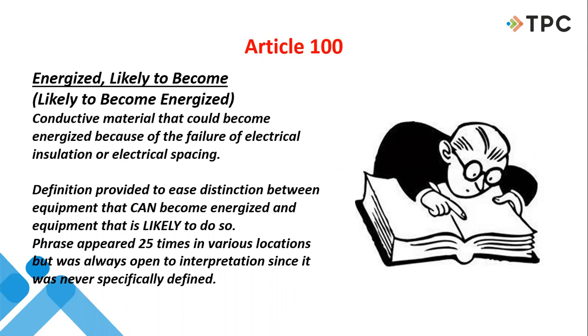Well, that's a very subjective approach. So with this definition, they had to clearly define what it means for something to be likely to become energized. And it simply means conductive material that could become energized because of the failure of electrical insulation or electrical spacing. So they're narrowing down what it is they're calling something that is likely to become energized. The key word here was likely. If you read in the second paragraph here, they needed to differentiate between equipment that can become energized and the equipment that we're discussing here that is likely to become energized. Big difference there, but they never actually differentiated between them.